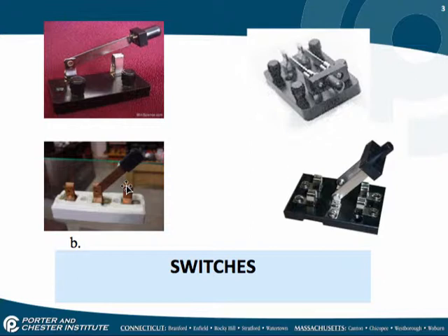In refrigeration, a closed switch would be like a thermostat that is in a space that's too warm. Okay, the thermostat is too warm, it closes, it turns on the compressor or the cooling circuit. When the space cools off, it opens, and thus you have an open switch, de-energizes the compressor. So I might as well introduce those two other terms while I'm at it. Energize and de-energize.